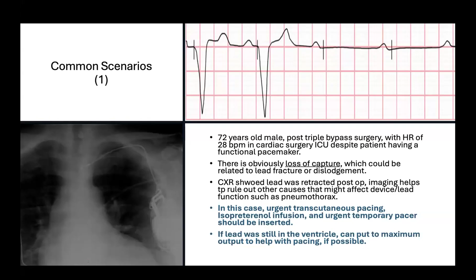So in this case, the patient is pacing dependent, as we could see here, then an urgent transcutaneous pacing, putting an isoproterenol infusion until we prepare for an urgent temporary pacemaker insertion. And if the lead was still in the ventricle, we can put the thresholds, or the output, to the maximum values, if that helps, if possible, just to buy some time. And then this lead has to be repositioned or replaced later on.